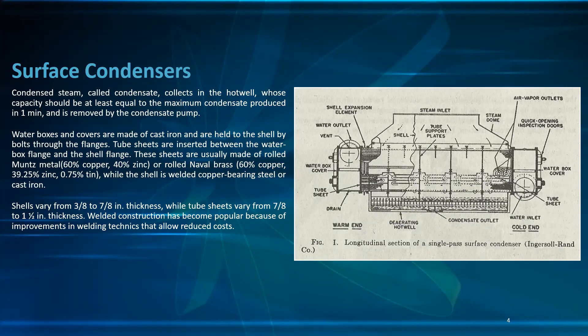Water boxes and covers are made of cast iron and are held to the shell by bolts. Tube sheets are inserted between the water box flanges and the shell flanges. These sheets are usually made of rolled Muntz metal — 60% copper, 40% zinc — or rolled Naval brass — 60% copper, 39.25% zinc, 0.75% tin. The shell is welded copper-bearing steel or cast iron, with shell thickness ranging from 3/8 to 7/8 inch, while tube sheets vary from 7/8 to 1.5 inch thickness.